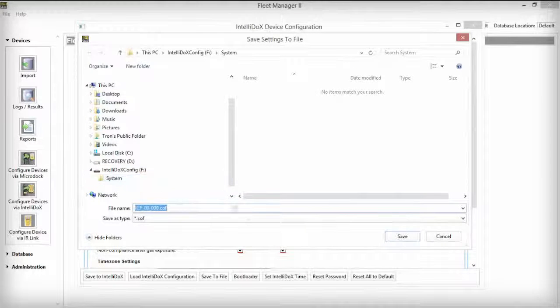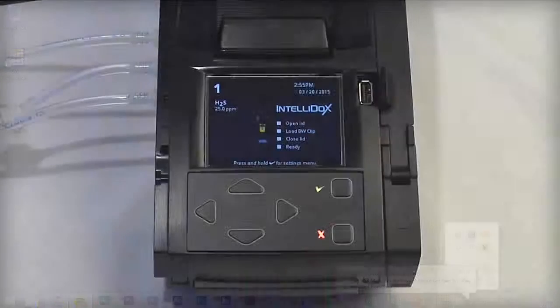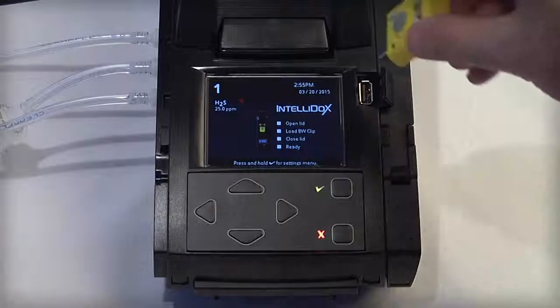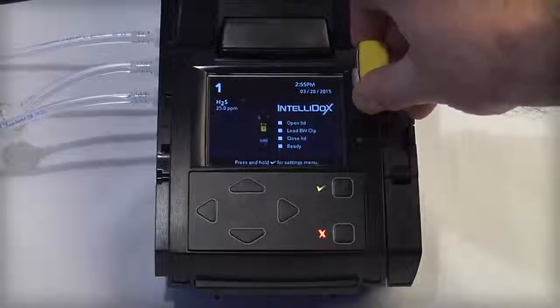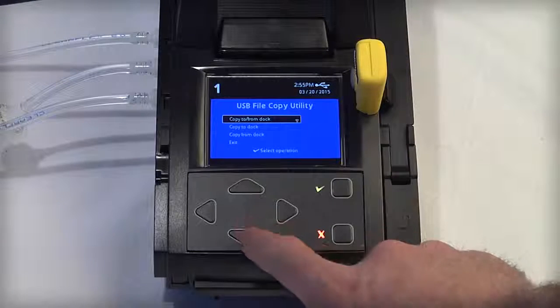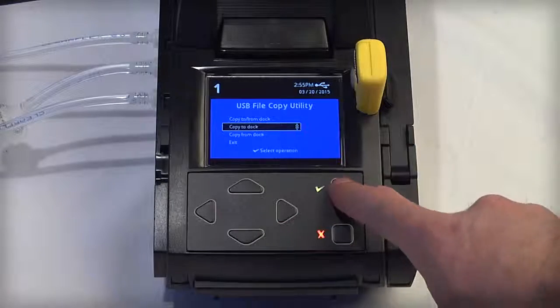Navigate to the System folder on your USB drive you created earlier and save your file. Eject your USB drive and insert it into the IntelliDoX module you want to configure. The USB File Copy Utility menu automatically appears. Use the arrow keys to select Copy to Dock and then press the green Check button.